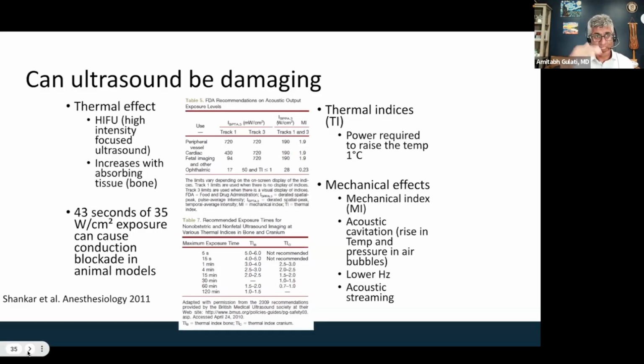But if you reduce that acoustic intensity, we tend to think of that as watts per centimeter squared, but this could be joules as well, depending on the units you choose. If we reduce it, but keep it higher than a diagnostic device, we can change the temperature to 41 degrees centigrade, 42 degrees centigrade, almost like pulsed radiofrequency, giving a way for heat to either dissipate or less vibration to maintain the heat in a therapeutic window, but not damage tissue.